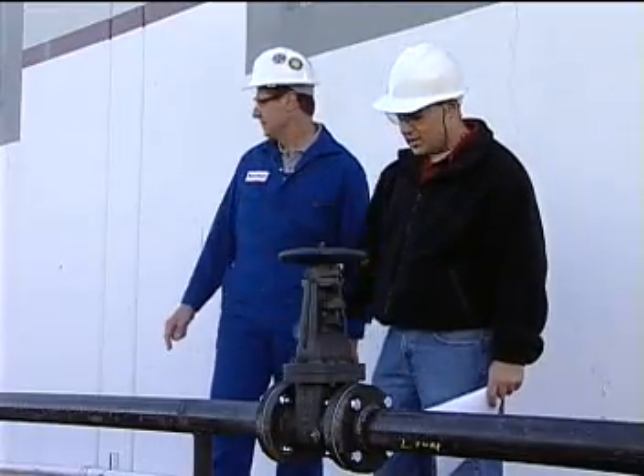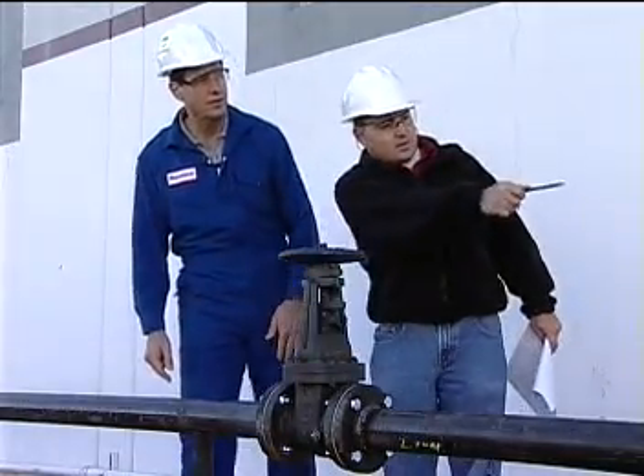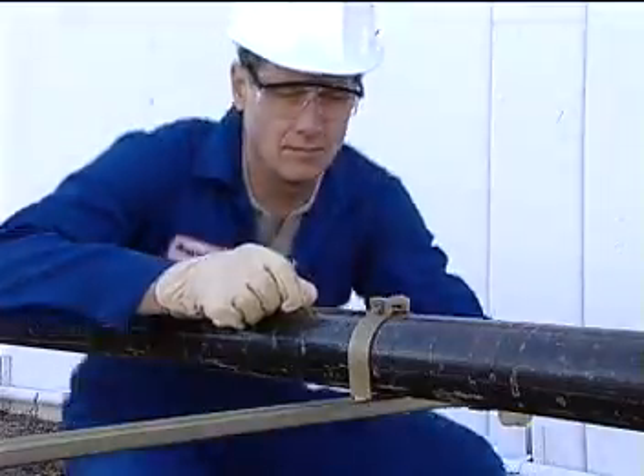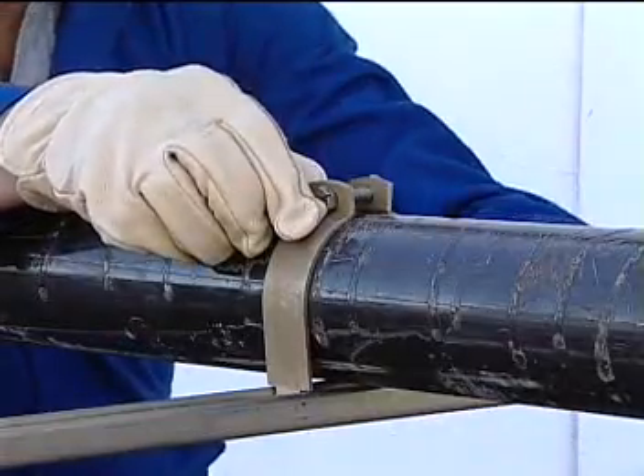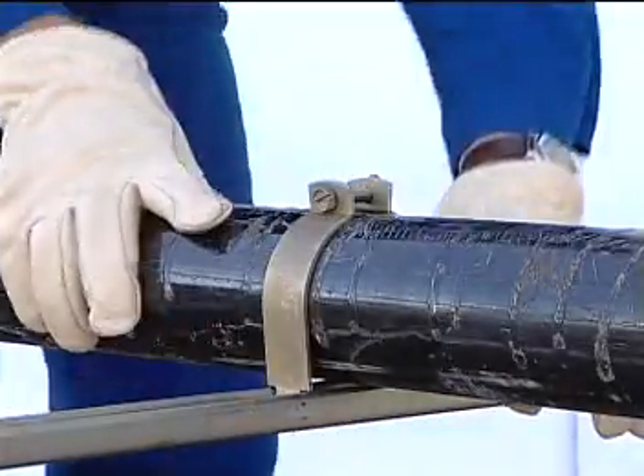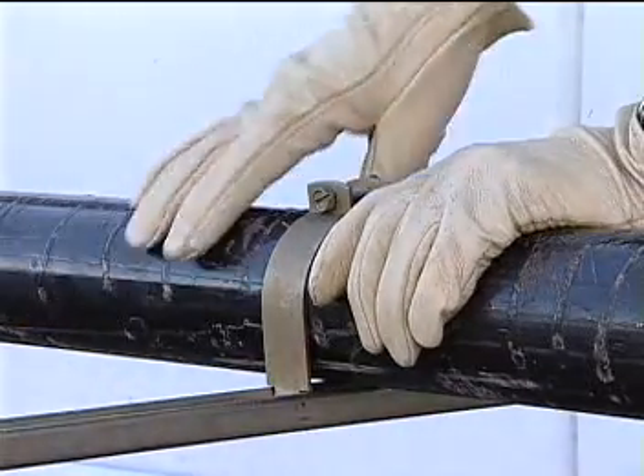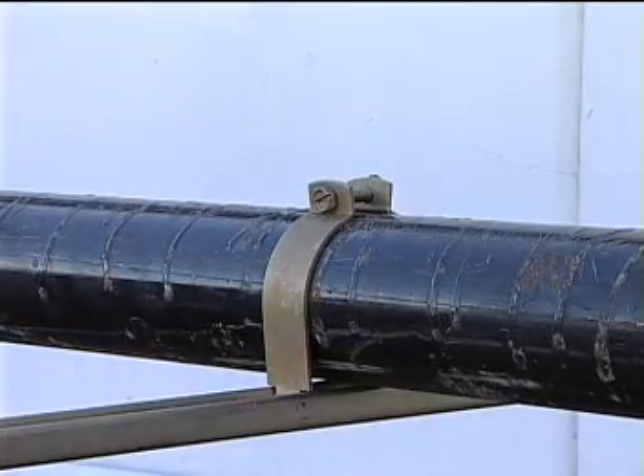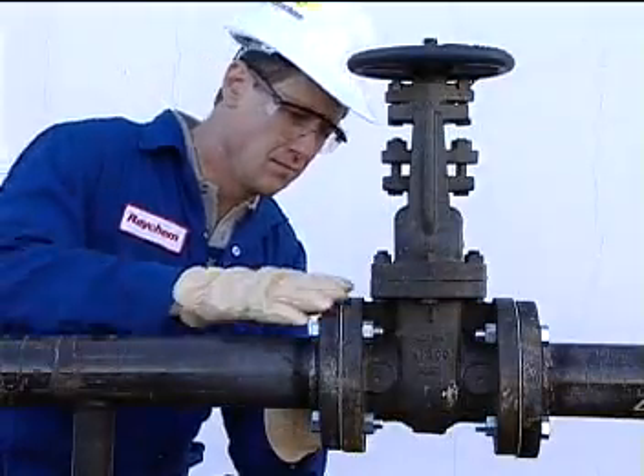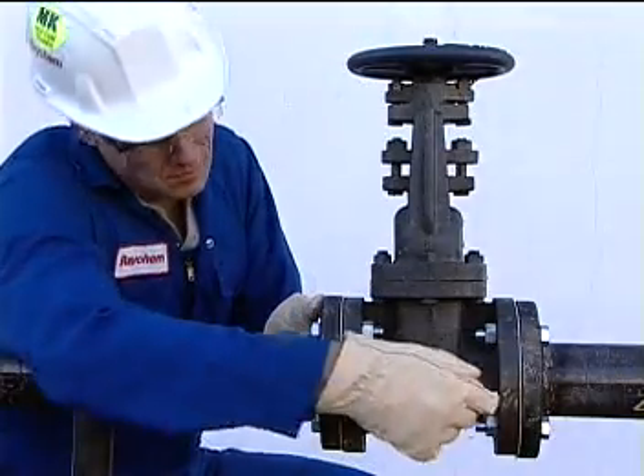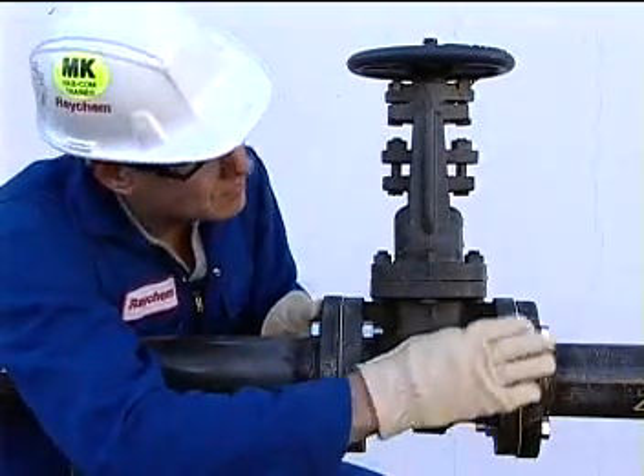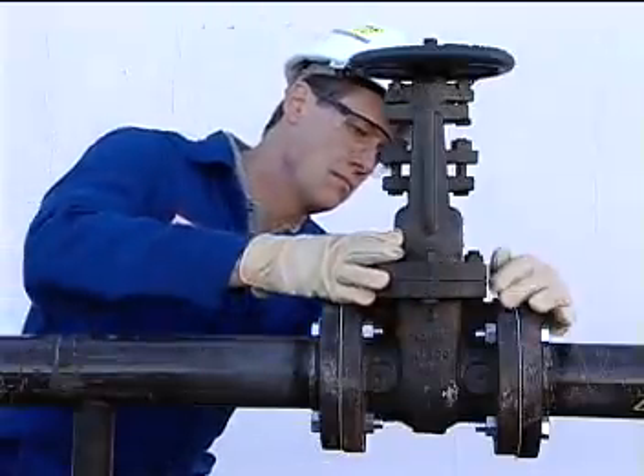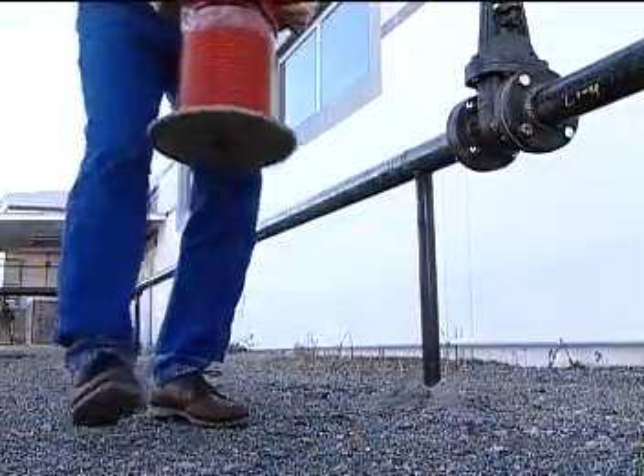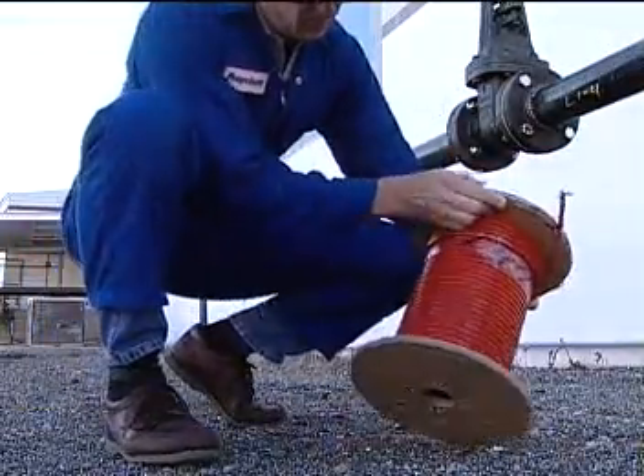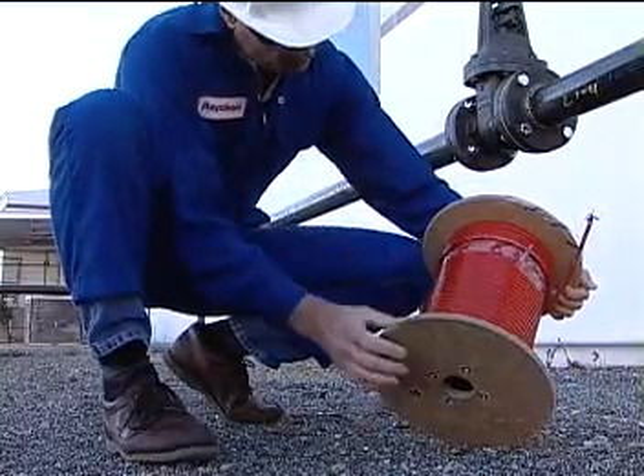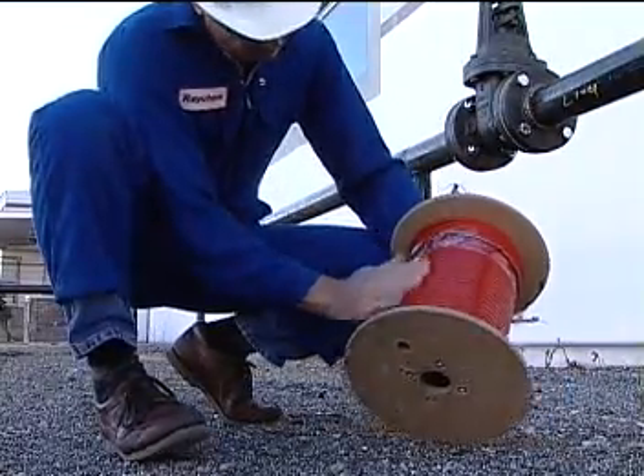Also, confirm that the hydro pressure testing has been completed, and then check to make sure that all piping, supports, and other attached structures are completely installed. Heating cables can be damaged by someone installing a support bracket over the top of them. Next, check to make sure that any newly painted pipe is dry, and be sure burrs or rough edges won't snag or cut the cable. Costly downtime can be avoided by inspecting the cable for nicks and cuts, as well as by checking other components for damage before they're installed.